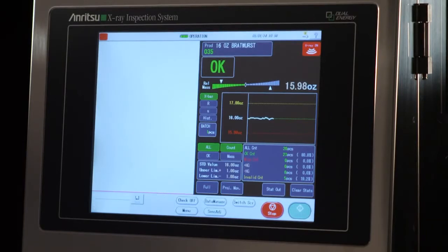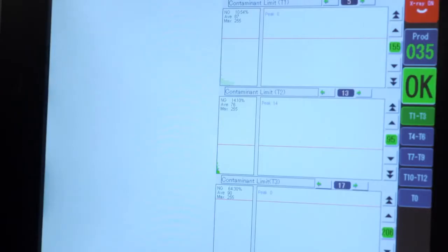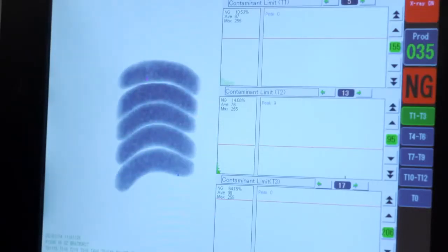Ultra HD and HD technology allows us to find very small metals in both food and pharmaceutical products. In a nutshell, it allows us to find 0.8 millimeter and below stainless steel detection in just about all food products. In thinner applications or pharmaceuticals, we can get down to 0.2 or 0.3 millimeter stainless.